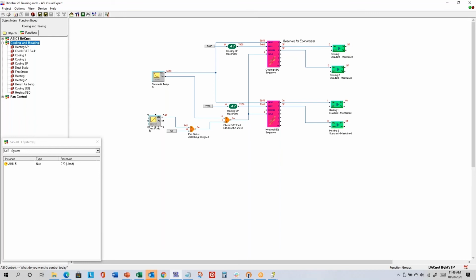No, if you could, can you just explain that interlock for me real quick? Yeah, so the interlock handle is used to say, don't allow the sequence to proceed if the interlock handle is 0, because I don't want the heating and the cooling to run if I don't have enough duct static pressure. Right? So if the duct static pressure went down to 0, as an example, I would not want my heating and cooling to run.